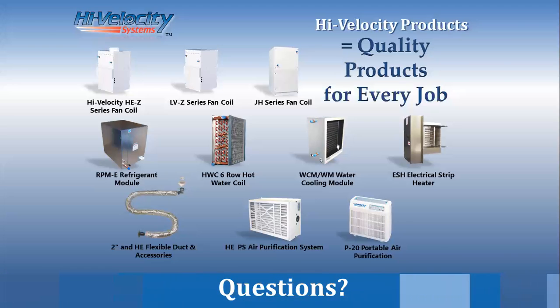It's something that we've been talking about for the entire existence of this company. So to some contractors, duct sealing is new. For our mature contractors, it's regular, everyday operation. With a high static duct system, if there's a place for that air to leak, it's going to find it, it's going to potentially whistle, and it's going to create an issue within your structure. So duct sealing is absolutely critical with a high velocity duct system.